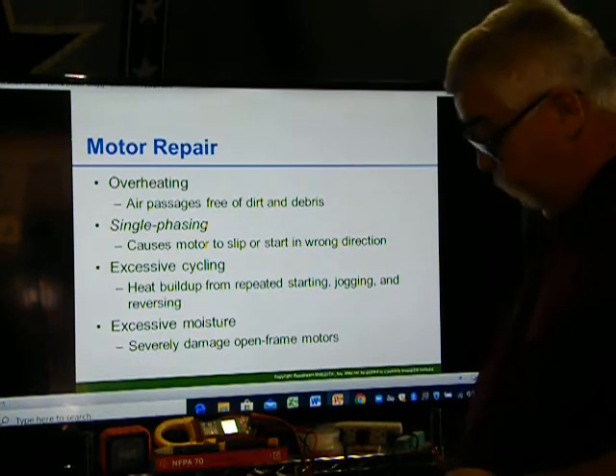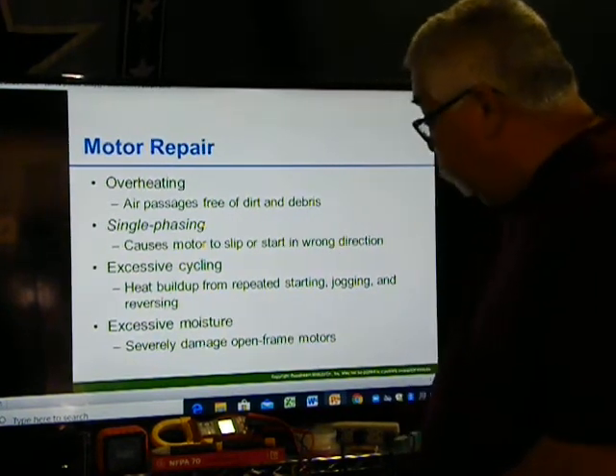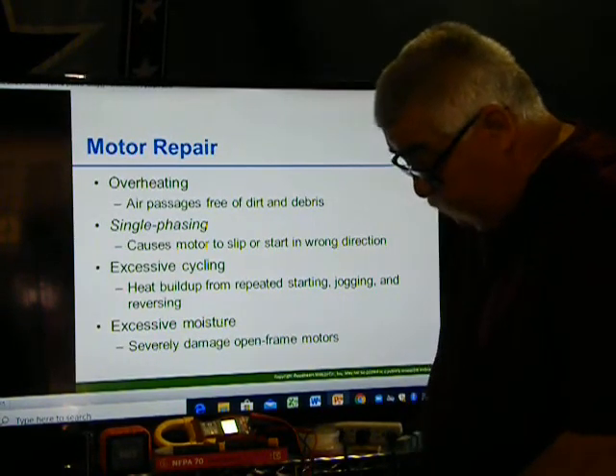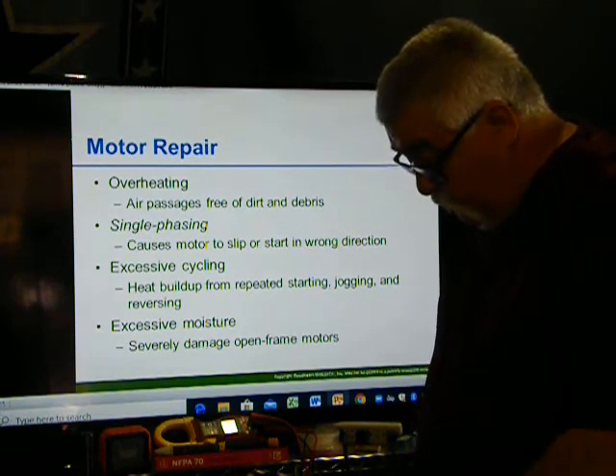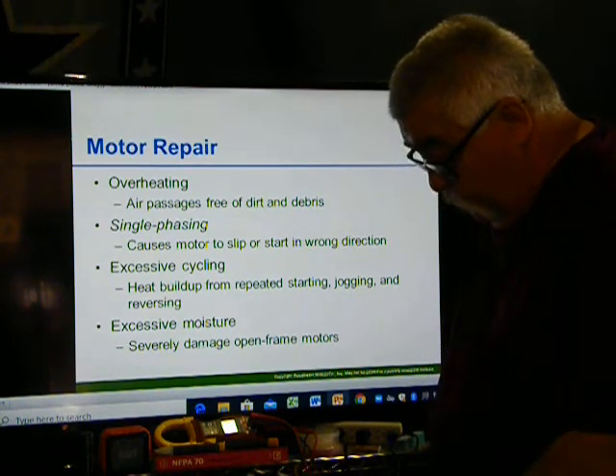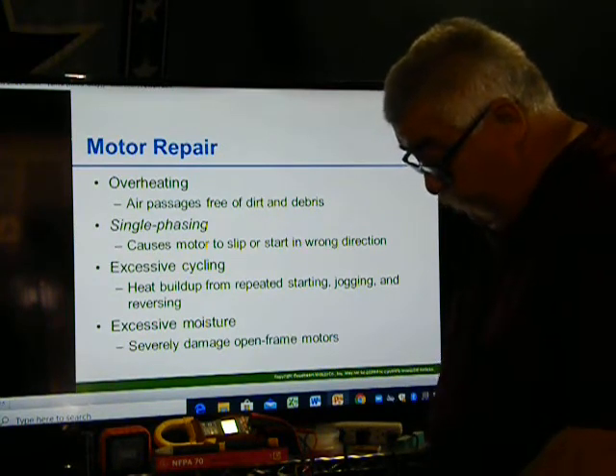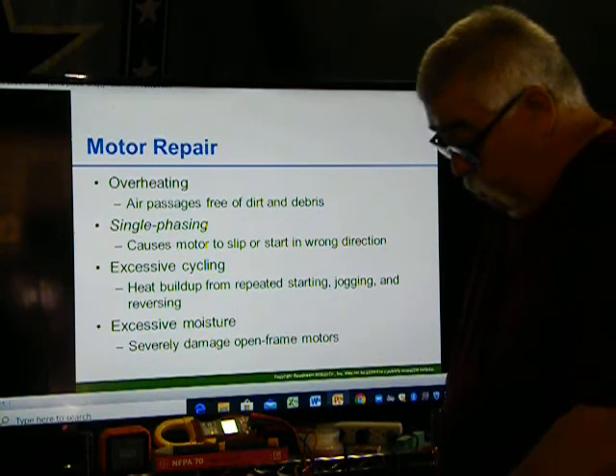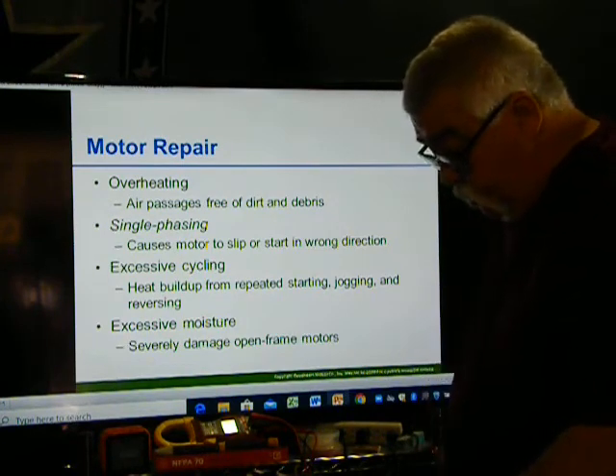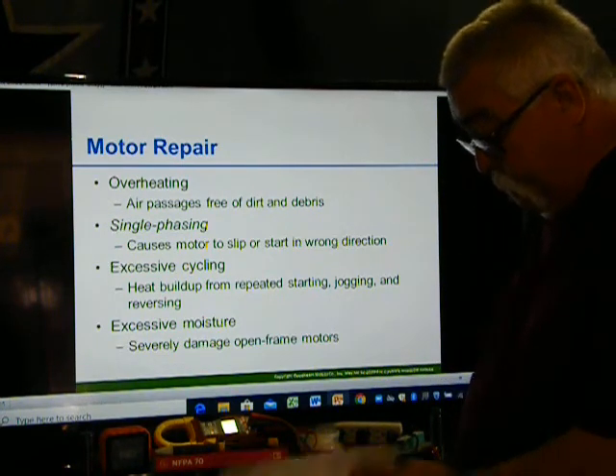Excessive moisture. Unless a motor is designed to be placed in a wet environment, as is the case with totally enclosed motors, it will not last long in such conditions. Moisture in any form can severely damage open frame motors. Precautions should be taken to protect motors from moisture in any form.